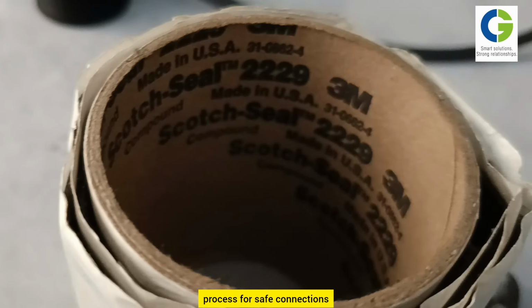Do not use only insulation tape for these connections. You need to follow the same process as for a submersible. Think of this as a kind of submersible pump, and based on that, connect the extension cable. Never plug the pump directly into a 3-pin socket. Always use a starter or panel based on recommendations. Select a starter based on the current rating mentioned on the nameplate.